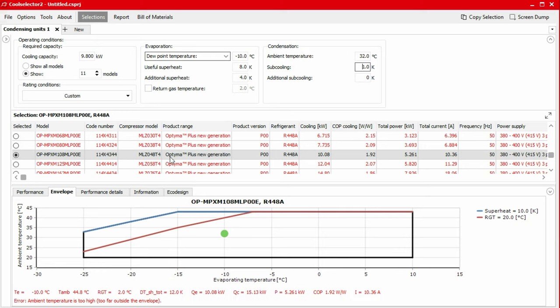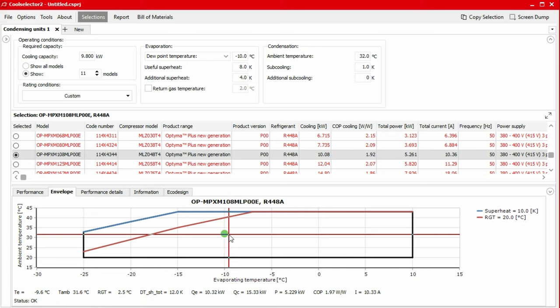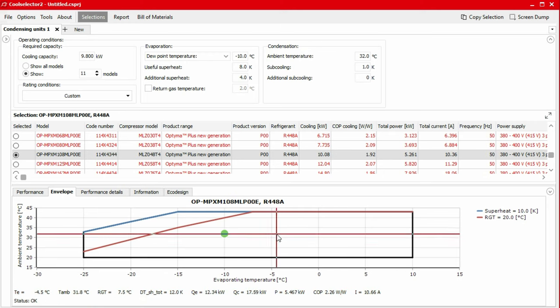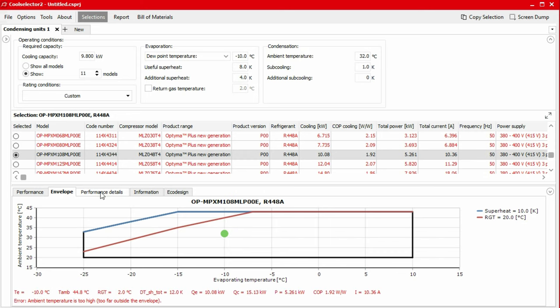Underneath the envelope, we have a legend which provides valuable information such as temperatures, cooling capacity and power consumption. As we move our mouse on the screen, we can see the value changing, representing changes to the condensing and evaporating temperatures. If the green dot appears near, on or outside the limitations, then you should reconsider your application selection.